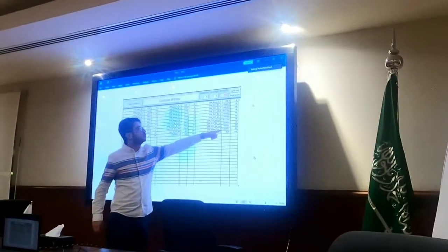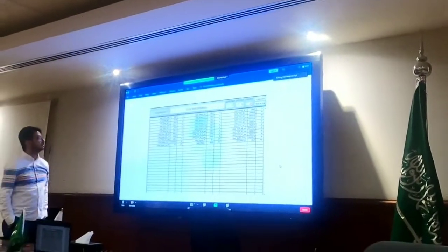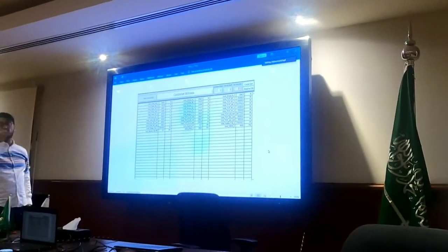And this is the total. Unit watts total: 136 kilowatts. Yes, this is the total, 136,332. Engineer Abdallah, what's the size of our breaker? 320. Yes, it is 400 adjusted to 320 as per Al-Fanar selection. Okay, it's a 400 ampere adjusted to 320.